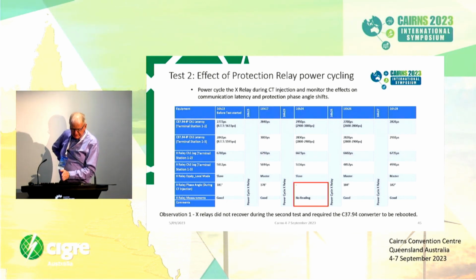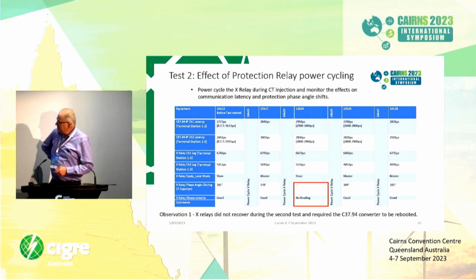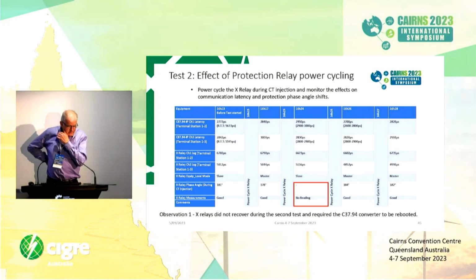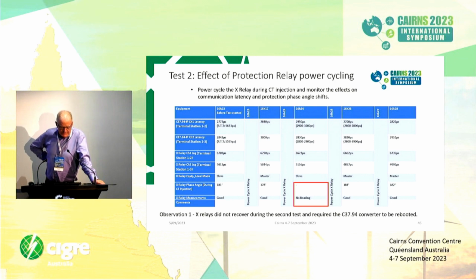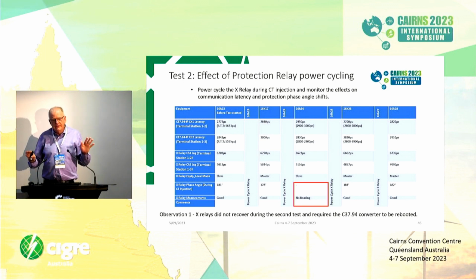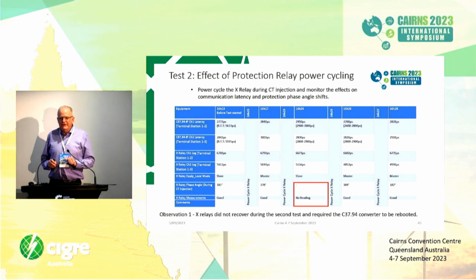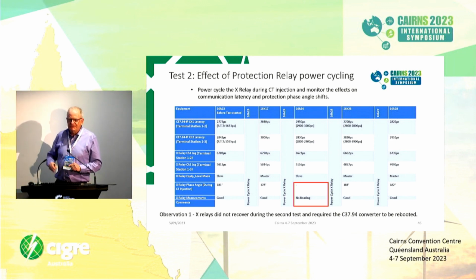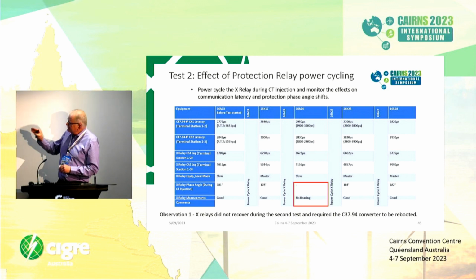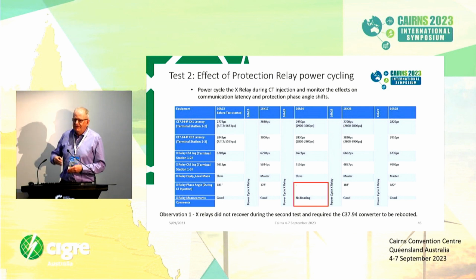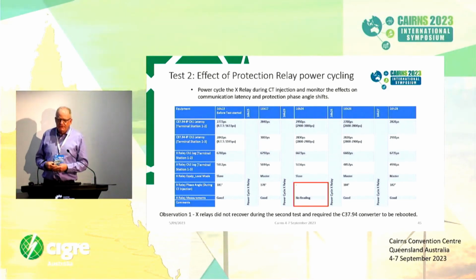Once again, the last 2 tests were successful, but during that test in the middle, we did observe that the relays didn't actually recover when the communications came back, and required the C3794 converter to be rebooted in order for the protection relay to start working again. We didn't really get to the bottom of why that occurred, and I must say this was during testing. We've never observed this in production. I guess the important thing is that it didn't cause any maloperation of the protection system other than the communications being down. And we know that if this was to occur in service, it's a matter of sending a protection technician to site just to restart the C3794 converter.